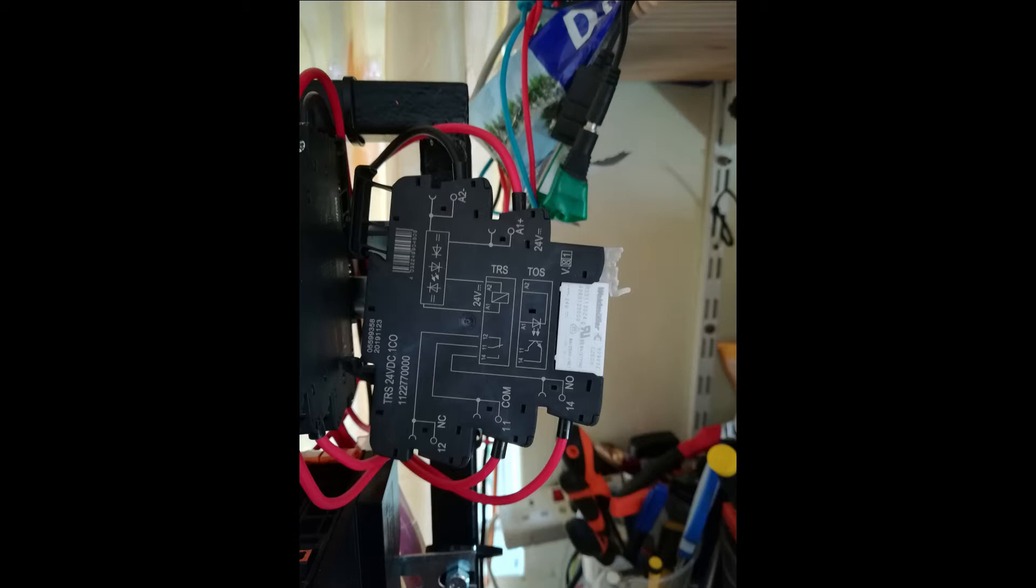The second reason is for isolation of circuits. We can use 24 volt DC on the coil, on one side of the relay, and on the other side we can use 230 volt or 440 volts.